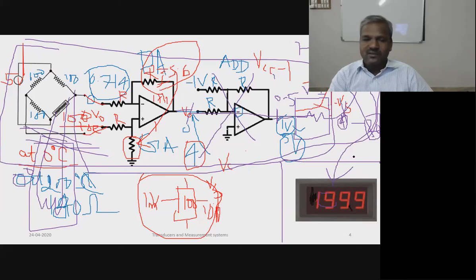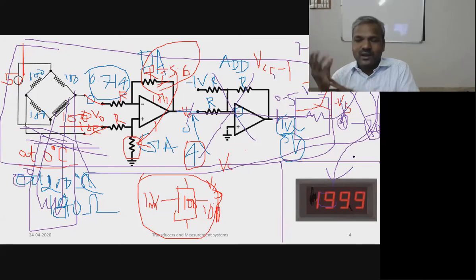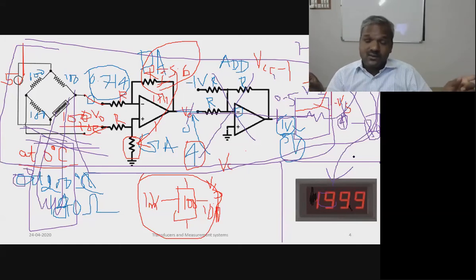So to avoid the failure of the instrument, and to identify problems in the cable circuits or grounding of the cables, we are having a range of 1 to 5 volt instead of 0 to 5 volt. If we have the transmission range 0 to 5 volt, when the sensor fails or there is a cut in the cable, we get 0. So we may not be able to identify whether that 0 represents 0 degrees Celsius or not. I hope you understand this concept, right?